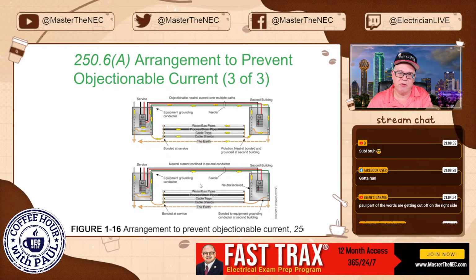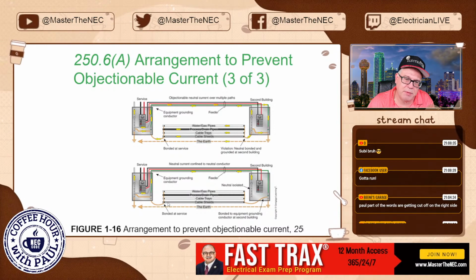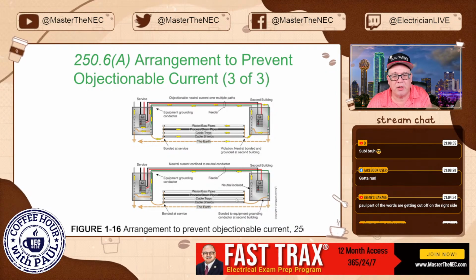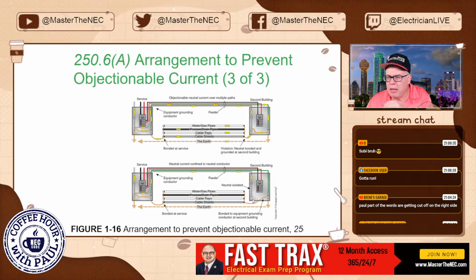But how do you rectify this? Well, look down here. Same scenario. So these assume that these are likely to become energized at the service. So the inspector says you got to bond them. So they're all bonded. But here at the other building, at their mutual systems, say maybe a campus setup or something, notice how the neutral is still isolated.